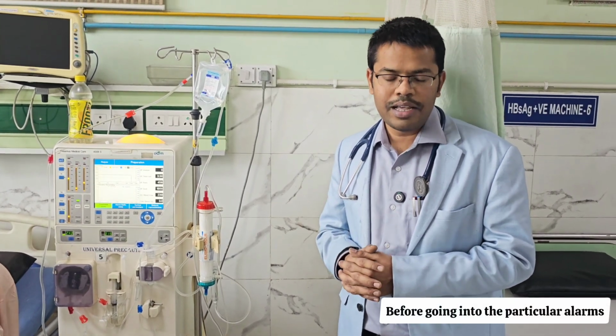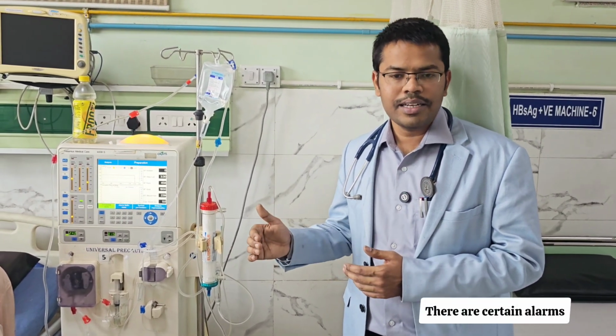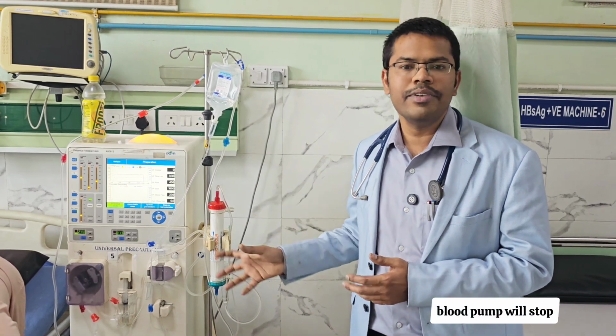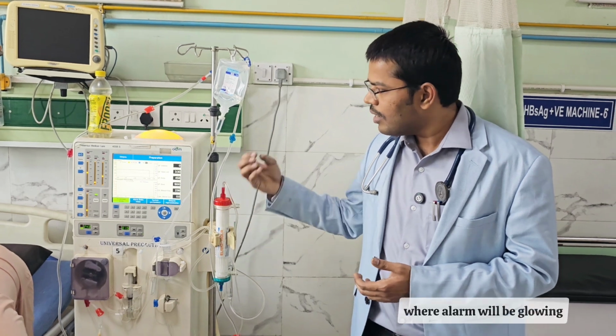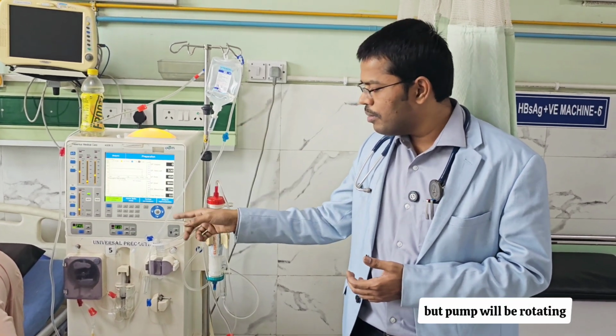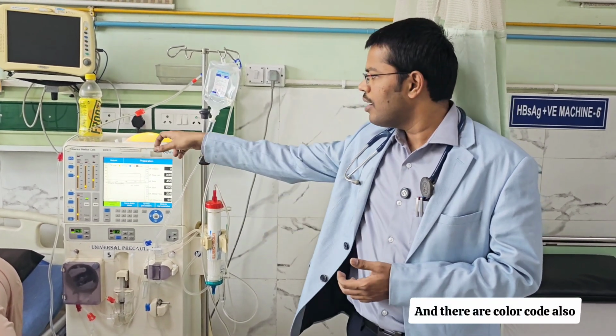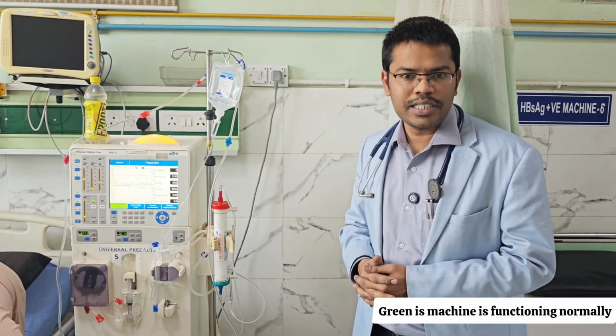Before going into the particular alarms, there are certain alarms where, once it is started, the blood pump will stop. The blood pump which is there will stop. There are certain alarms where the alarm will be glowing but the pump will keep rotating. There are also color codes, sometimes orange, red, green. Green means the machine is functioning normally. Orange and red are the visual representation of an alarm. Suppose in the unit 20 or more machines are there, by sitting at the console only you can see which machine is having what issue.